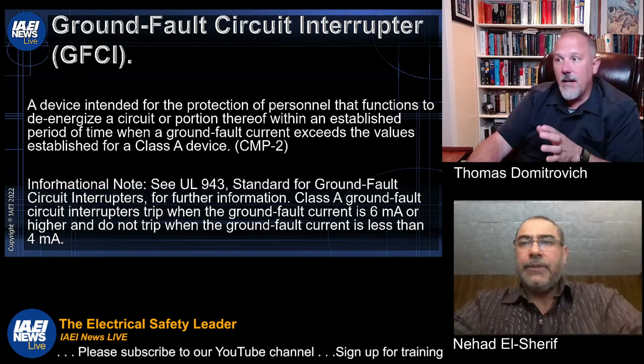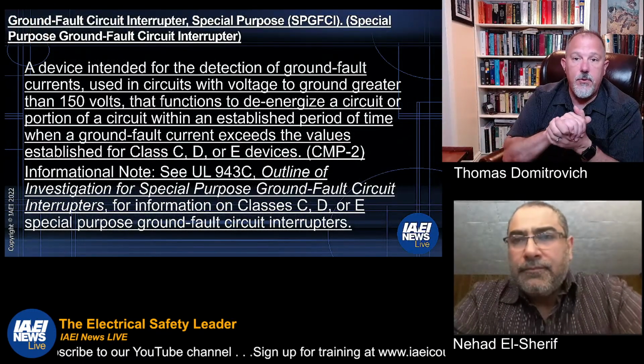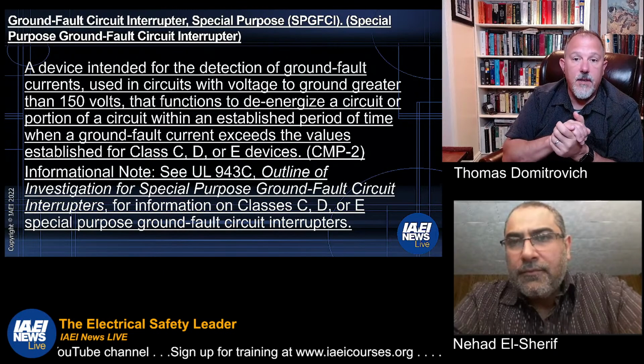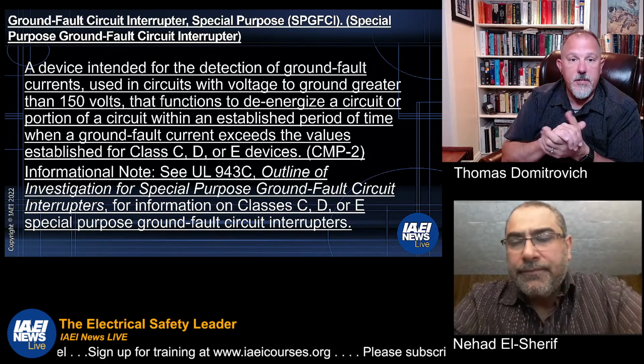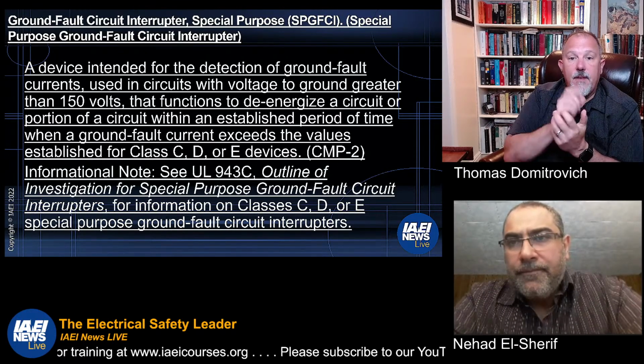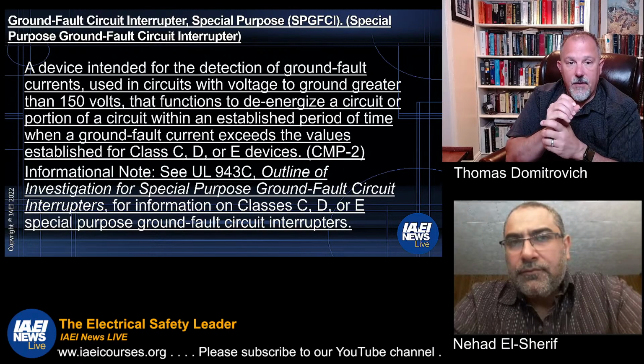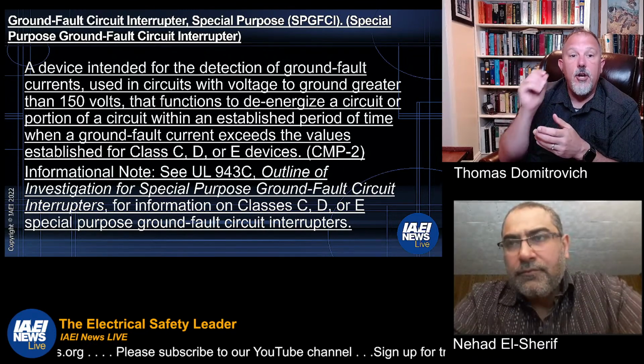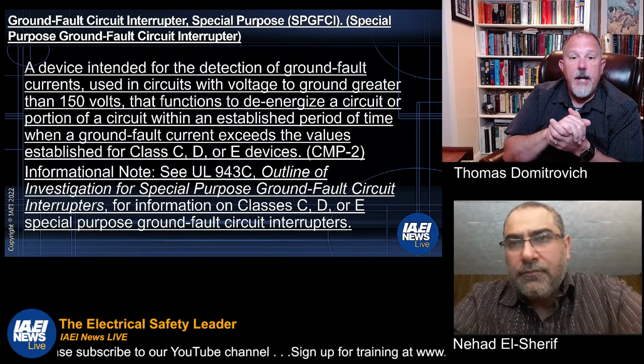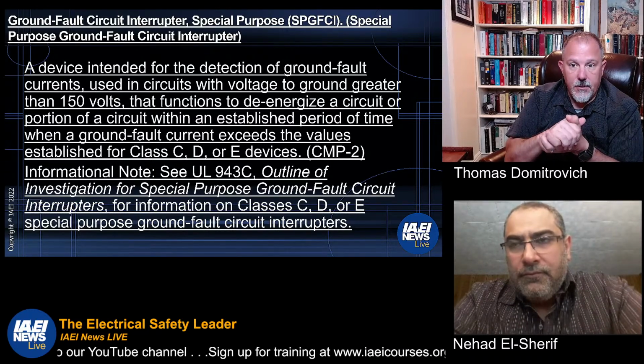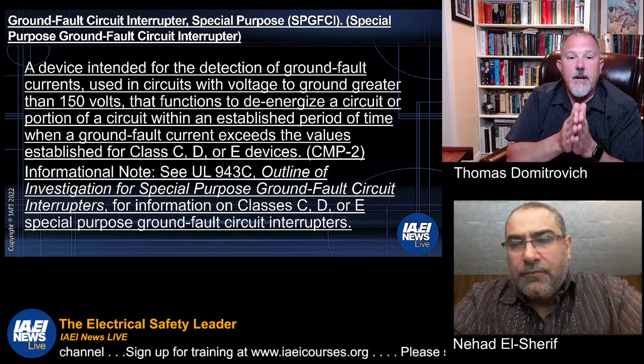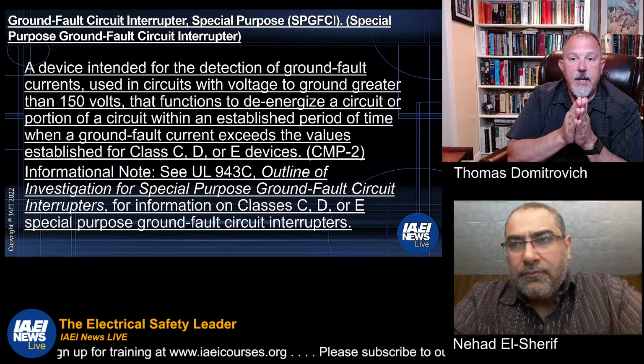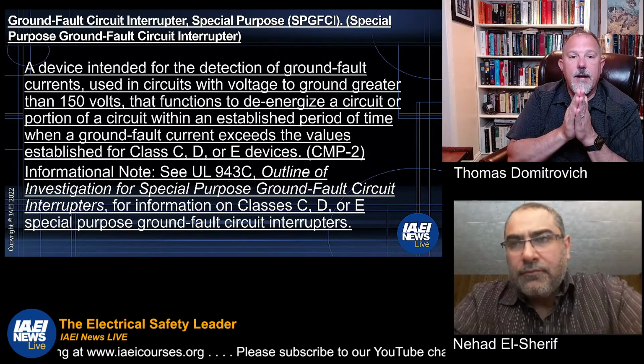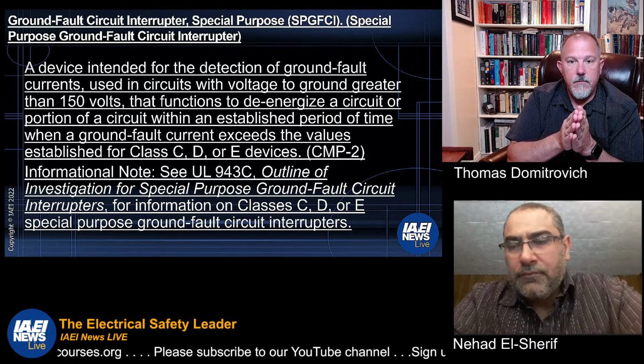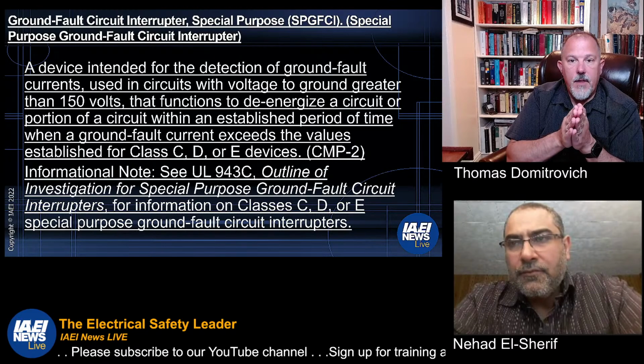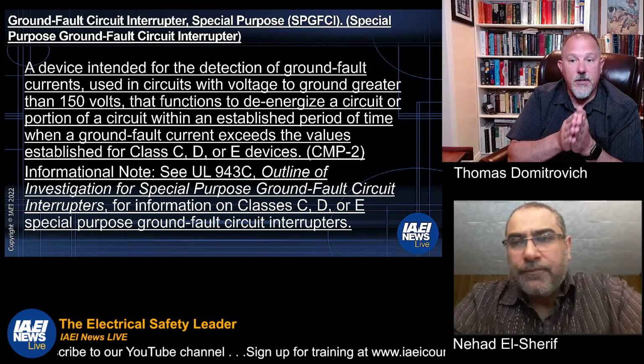Now let's talk about a new definition that was proposed and has been accepted for the 2023 code cycle. This is the special purpose GFCI. The definition says it's intended to detect ground fault currents in circuits at a voltage to ground greater than 150 volts, and it functions to de-energize a circuit. Since it's a voltage greater than 150 volts to ground, this would not be a 120 volt single phase circuit.